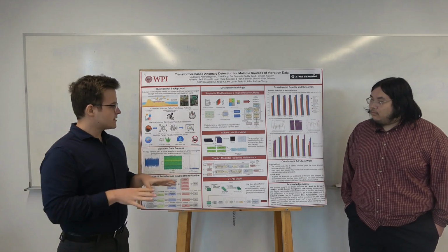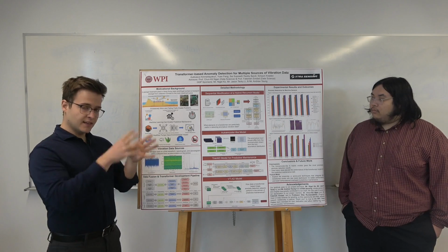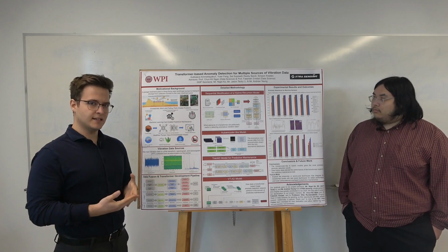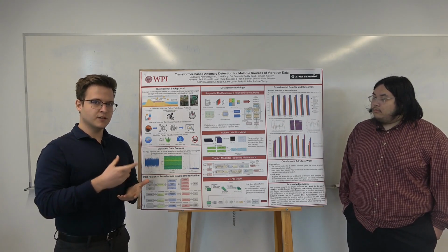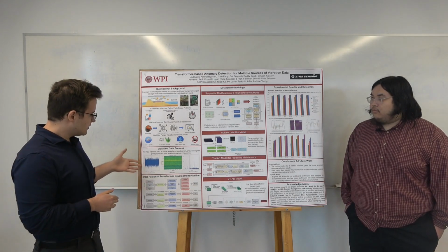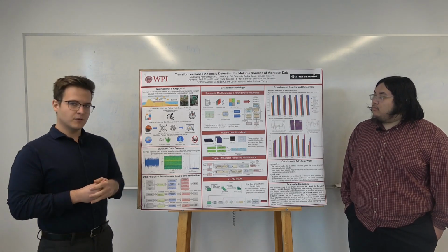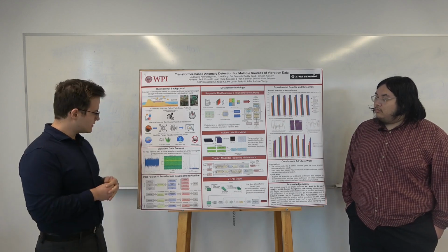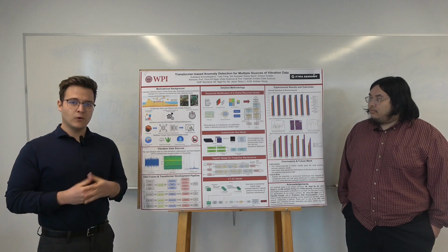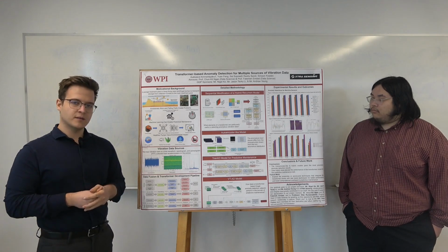Now, the way that Xtra Sensing does this is they have installed accelerometer sensors in the pumps at the different locations of the pumps, which continuously collect data on the vibration emitted from the normal operations of these machines. And these vibrations here are represented in the time waveform as raw data, meaning that for every unit of time, we can see how strong the force is experienced by these sensors from these vibrations.